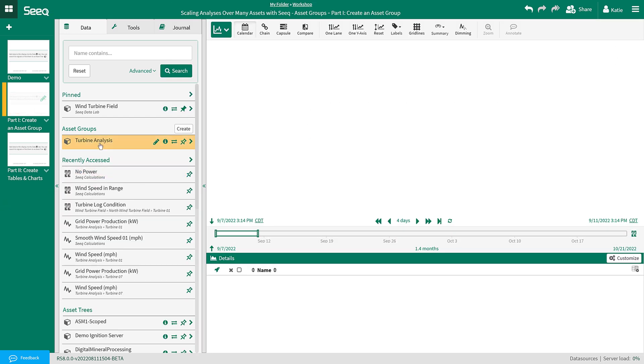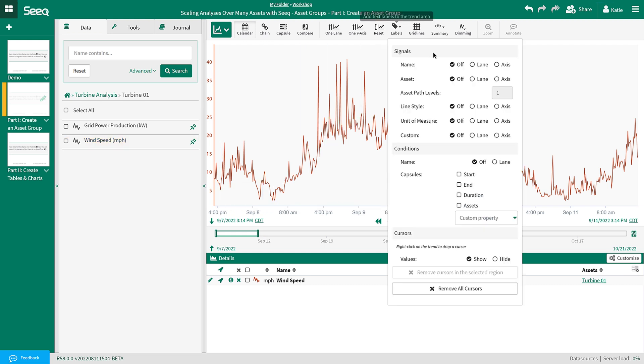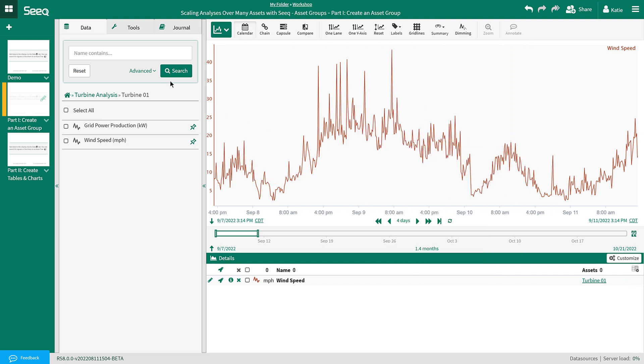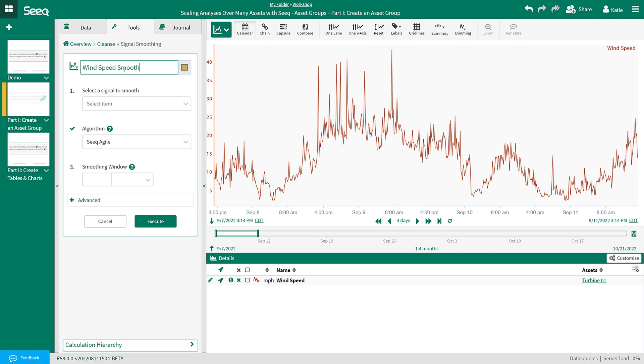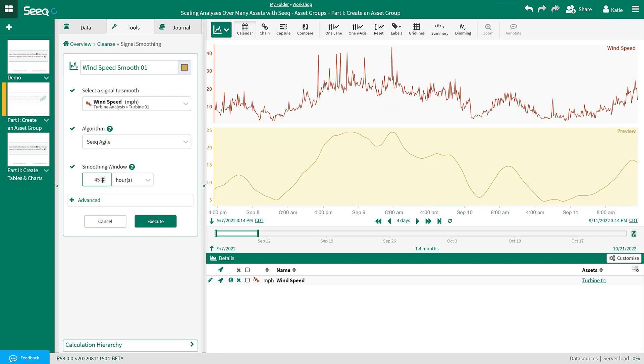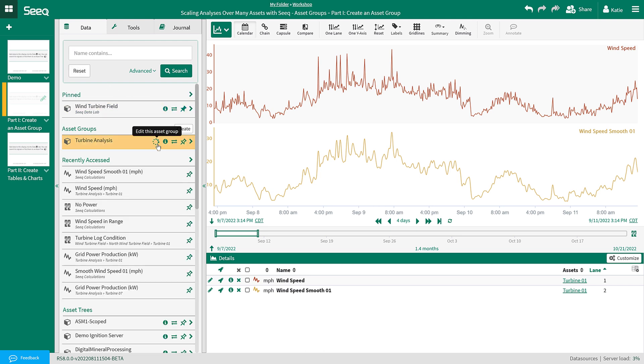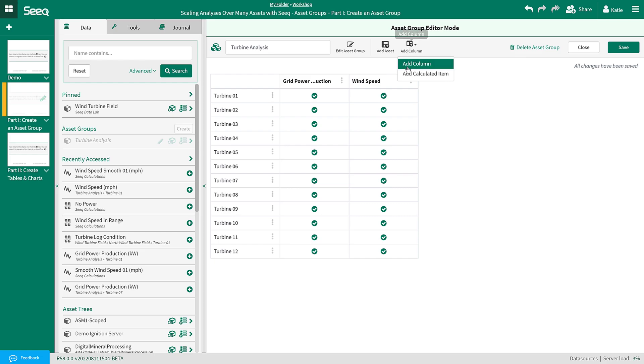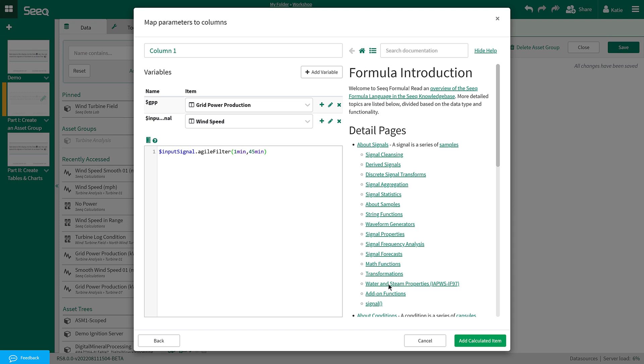Now I am going to start adding calculations into the asset group. First I will add wind speed for turbine 1 from the asset group to the trend. For this analysis I want to smooth all the wind speed signals. I will start by first creating this calculated item using tools, then add it to the asset group. Here I will use the signal smoothing tool, select the signal I would like to smooth, and apply the agile filter. Now I will open the asset group's editor, select add column, add calculated item, existing Seeq item, and select the item smooth wind speed. This will copy the formula from that item and open a formula window. If you are not familiar with Seeq formula, I recommend checking out the resources linked in the description of this video.